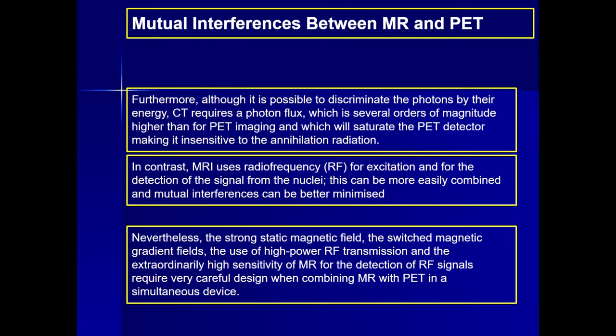Furthermore, although it is possible to discriminate the photons by their energy, CT requires a photon flux which is several orders of magnitude higher than that for PET imaging, and which will saturate the PET detectors, making it insensitive to radiation. In contrast, MRI uses radio frequency (RF) for excitation and for detection of signal from the nuclei. This can be more easily combined and mutual interference can be better minimized. Nevertheless, the strong static magnetic field, the switched magnetic gradient fields, the use of high power RF transmission, and the extraordinarily high sensitivity of MR for the detection of RF signals require very careful design when combining MR with PET in a simultaneous device.